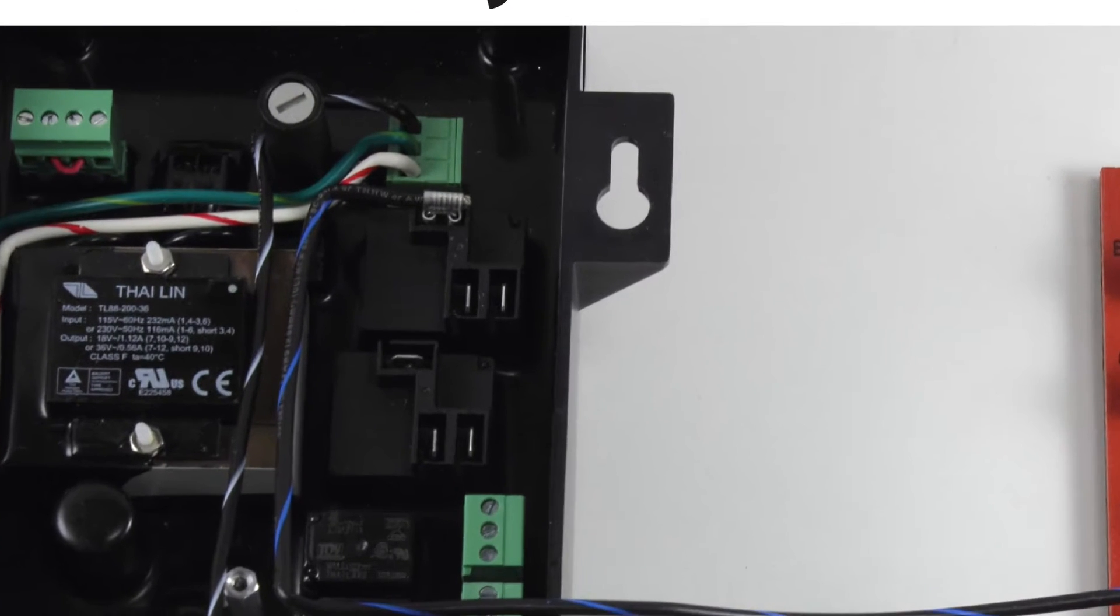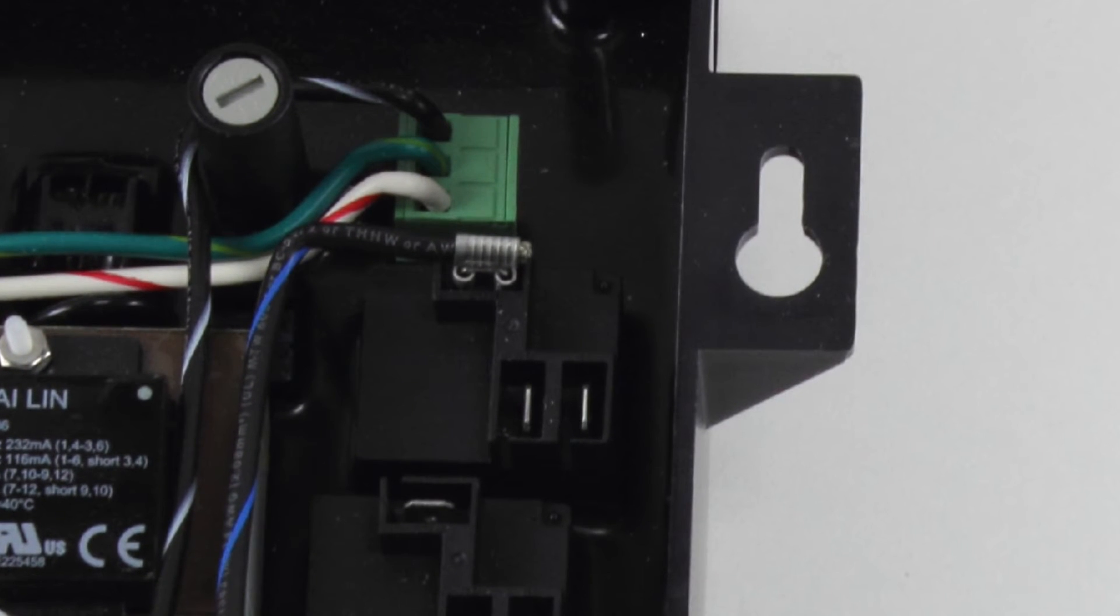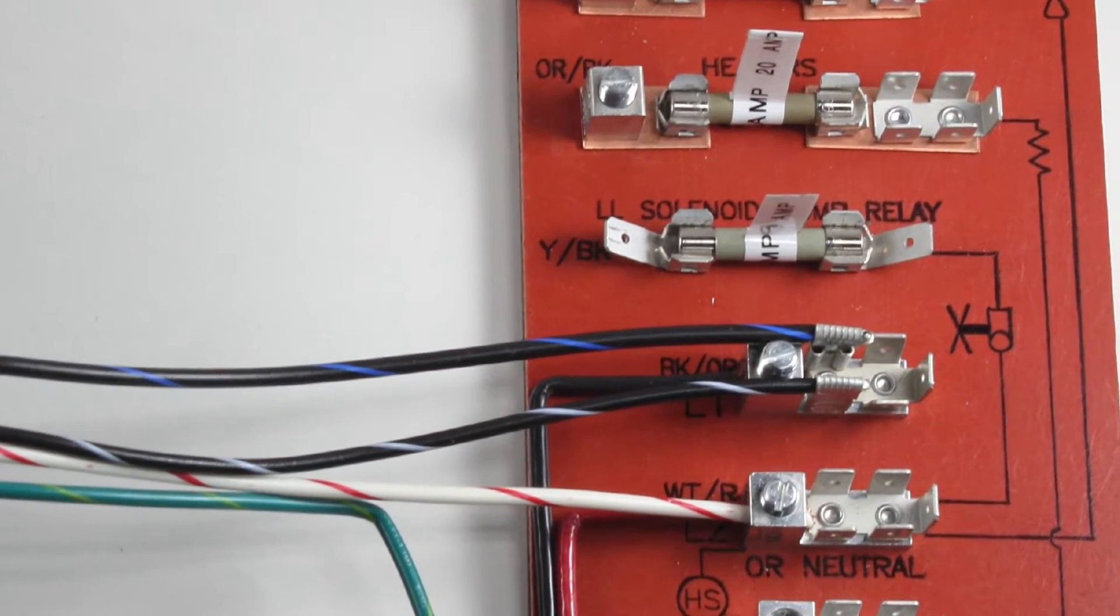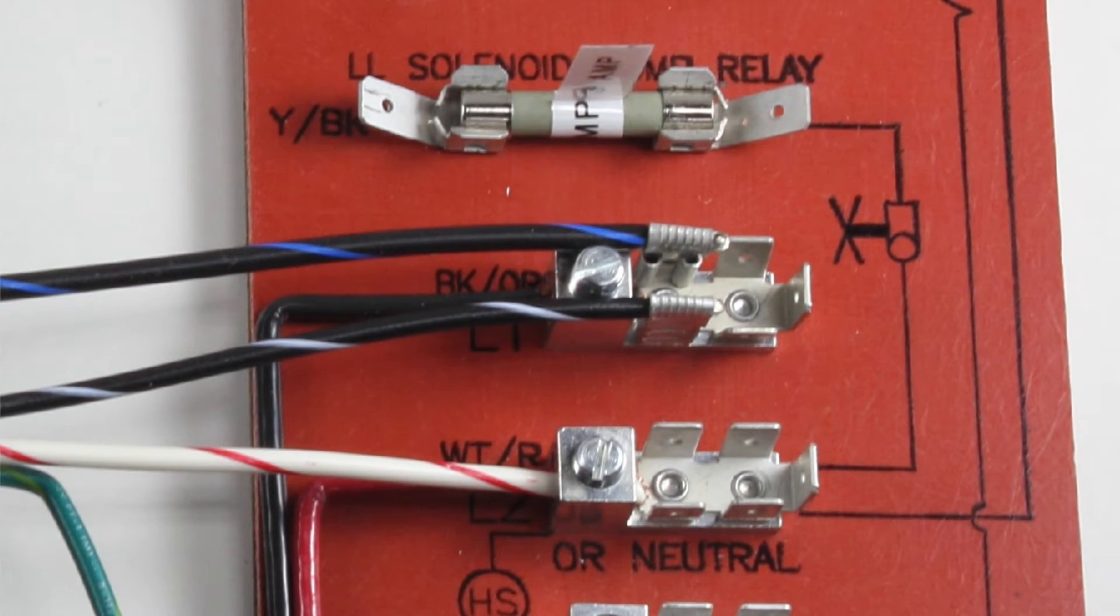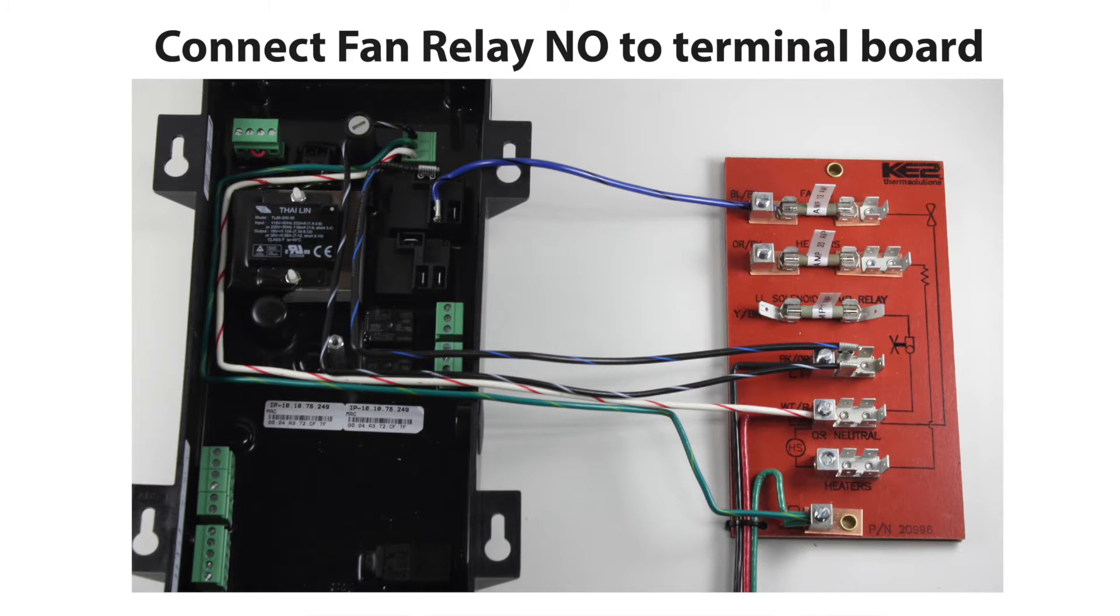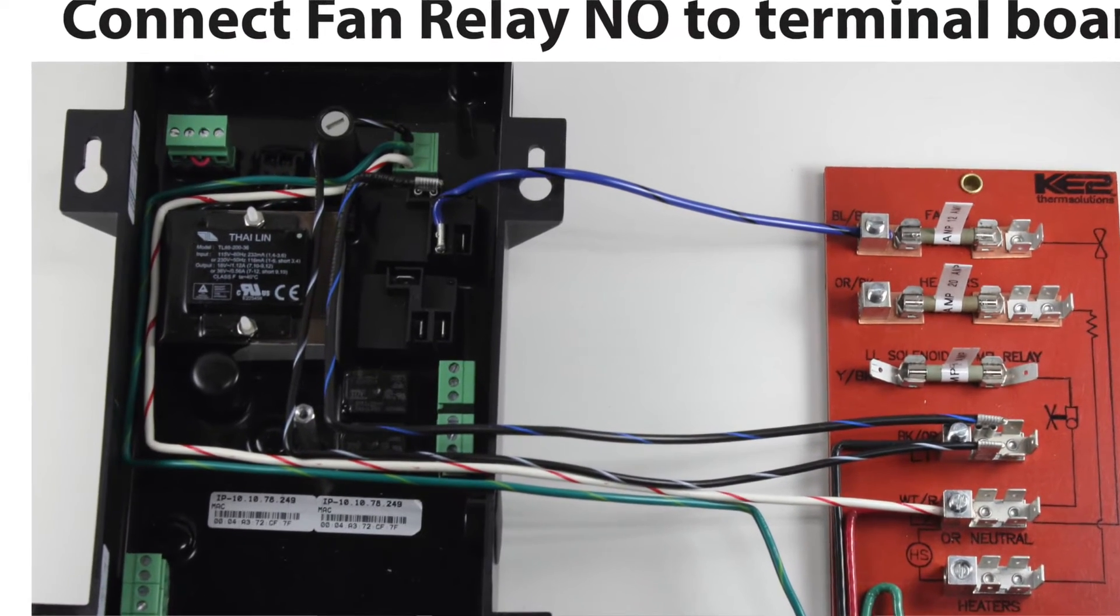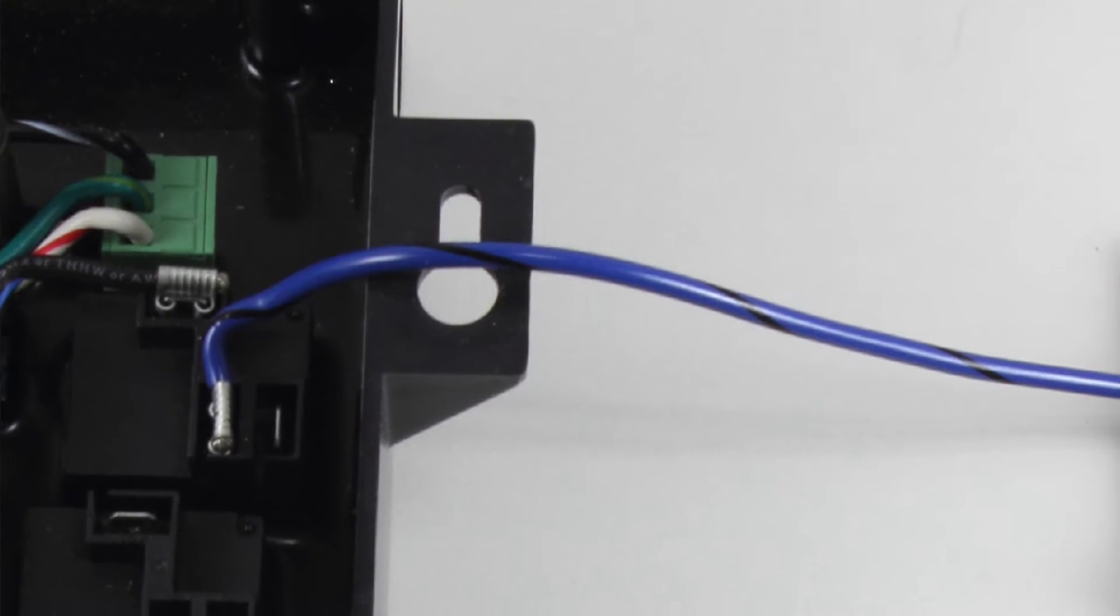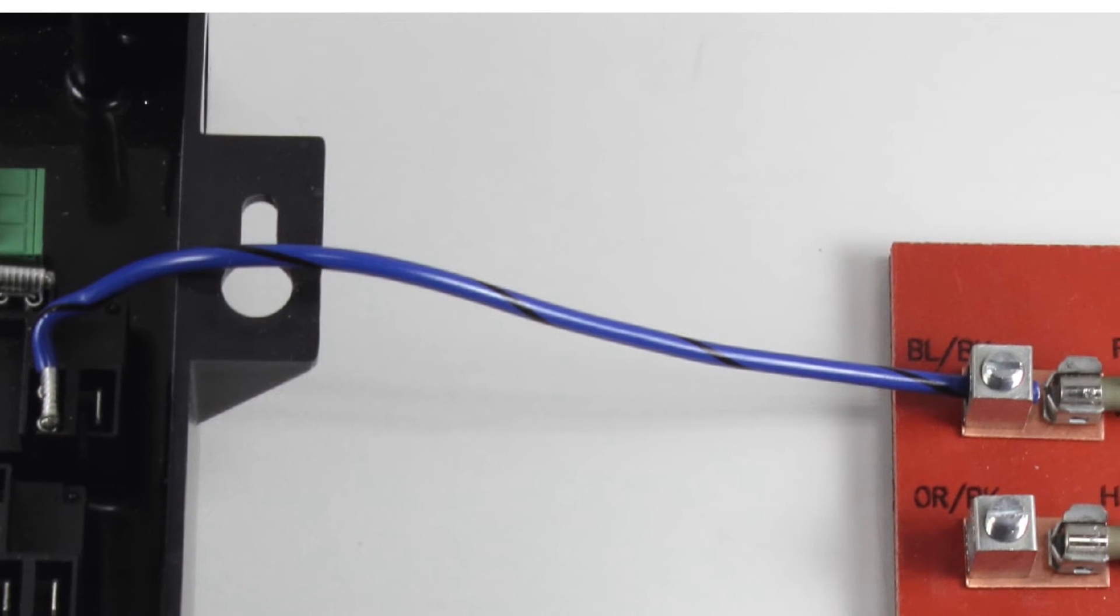Next, the fan relay dry contact needs power provided to the common terminal. Connect the line 1 on the terminal board using the black with blue stripe. Wire the common on the fan relay as shown. Connect from the fan relay on the normally open set of contacts using the blue with black stripe. Wire to the blue-black location as shown on the terminal board.